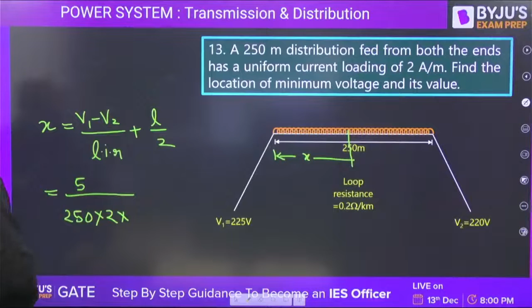Just put the values. 225, 220, it is 5. What is the length of the distributor? 250. What is the current loading? 2 ampere per meter. What is the resistance per unit length? So no need to worry because loop resistance is directly mentioned. So it is 0.2, but it is per kilometer. So divide by 1000 because we have to write per meter. Plus L by 2. So it is 125. To solve this, I think you must be getting 175 meters.